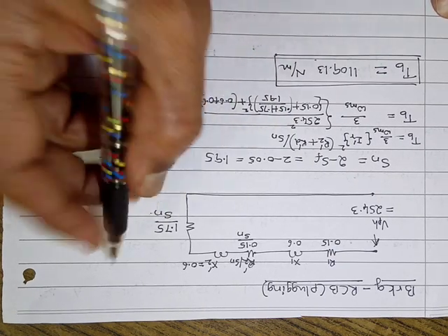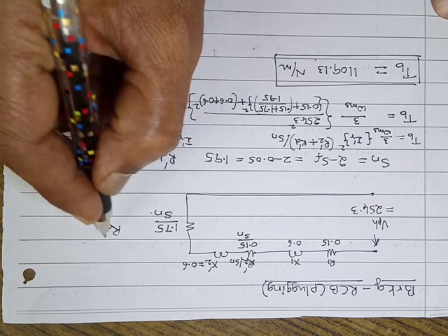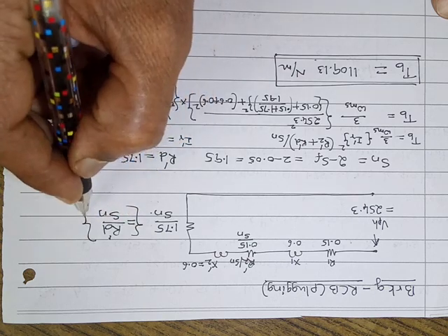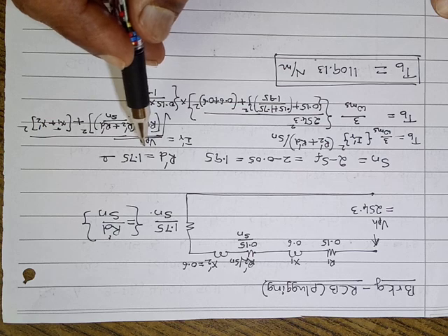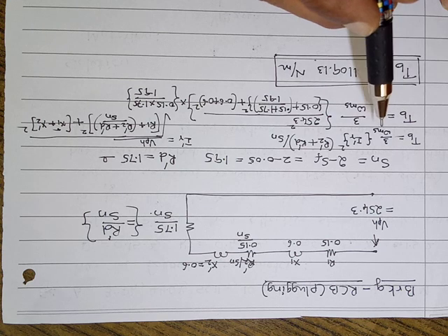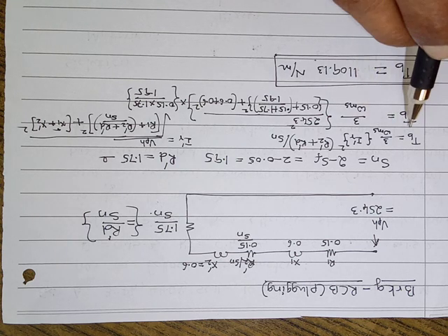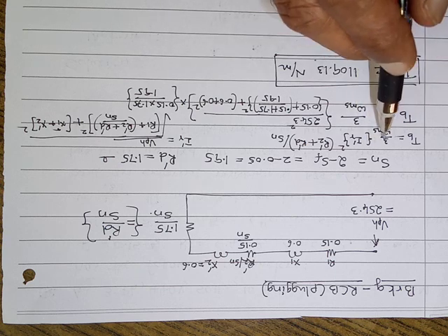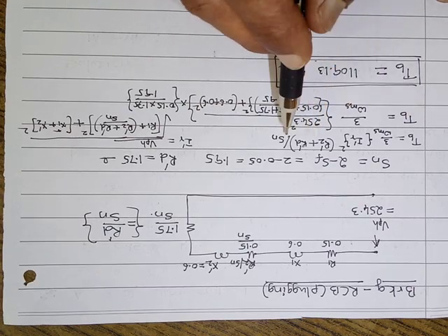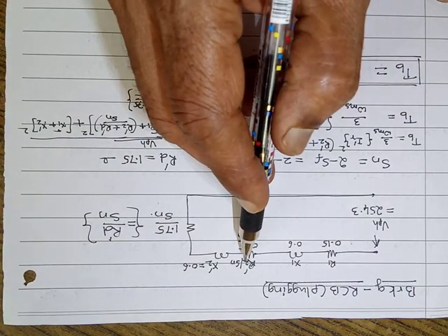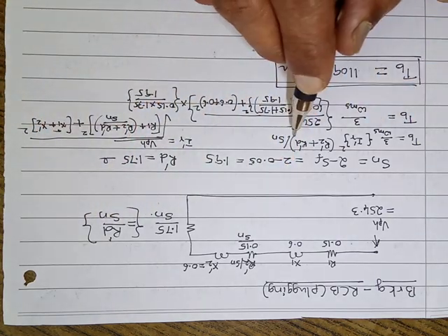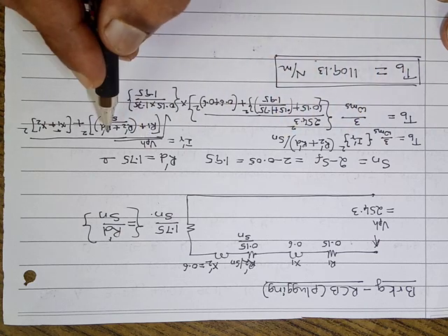And the additional resistance is RD dash divided by Sn. RD dash is already given, 1.75. Therefore, we can find what is asked in the problem, braking torque. What is the expression for the braking torque? Braking torque equals 3 divided by omega ms, IR dash square, into R2 dash plus RD dash divided by Sn. That is the equation.